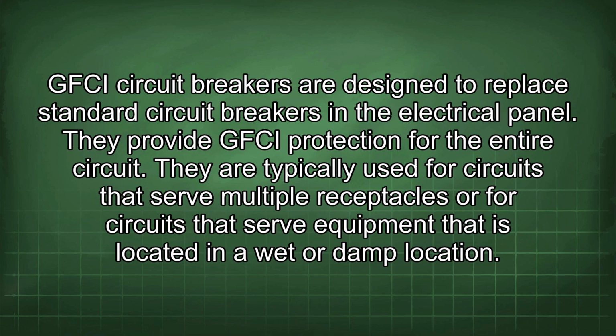GFCI circuit breakers are designed to replace standard circuit breakers in the electrical panel. They provide GFCI protection for the entire circuit. They are typically used for circuits that serve multiple receptacles or for circuits that serve equipment that is located in a wet or damp location.